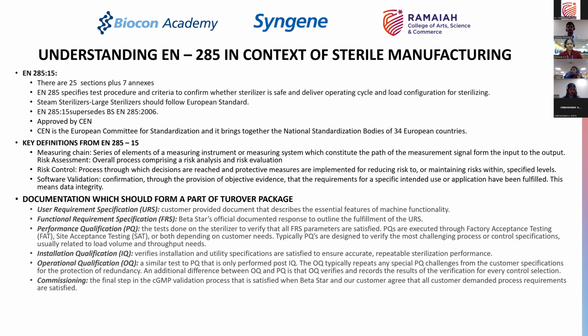It cannot be done at a client factory or the manufacturing site for sterile products, right? So you will do all the tests which ensure that your criteria of the URS and the DQ are met, and anything which is critical from a perspective of rectification at the vendor's factory and cannot be done at your site is definitely checked.